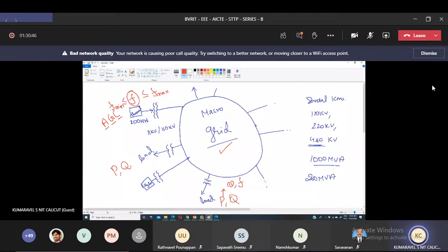Voltage also has a lower margin and a higher margin value. For that, we naturally have what is called an AVR, automatic voltage regulator. In the transmission system, we have the OLTC, on-load tap changing transformer. We use tap changers to control the voltage, so that we control voltage and frequency within permissible limits, maintaining stability of the whole power system.